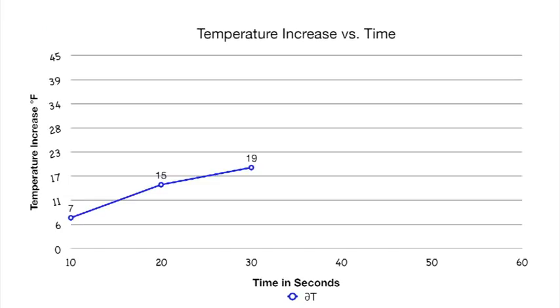As a final piece of information, we wanted to see how much temperature rise occurs over time. All our prior temperature experiments were for 10 seconds. This time we varied from 10 seconds up to 60 seconds using a 3mm thick plate at 3mm air gap. At 10 seconds, we got a 7.2°F rise. At 60 seconds, it was all the way up to 40.3°F in just one minute. This gives you an idea of the thermal consequences in eddy current applications — the faster you rotate and the more work it takes to spin, the higher the temperature will go.